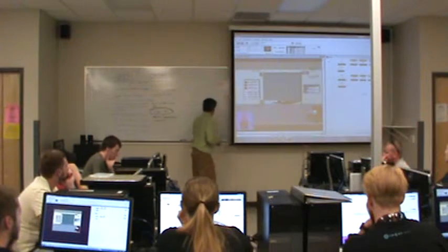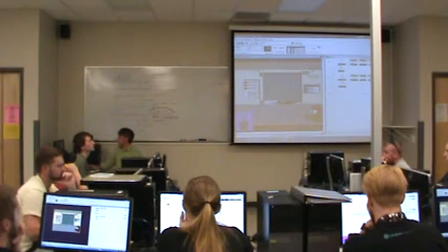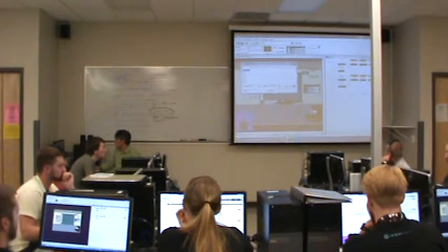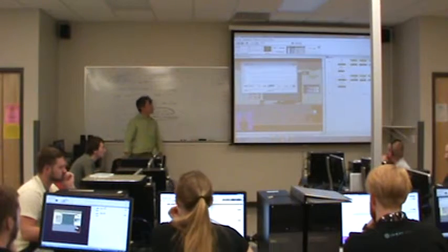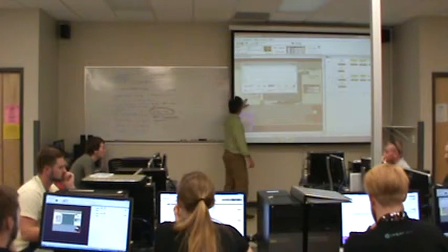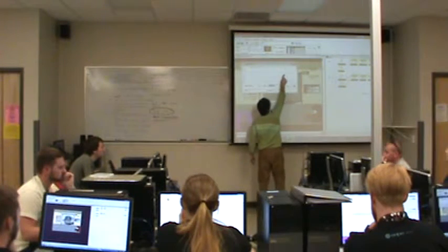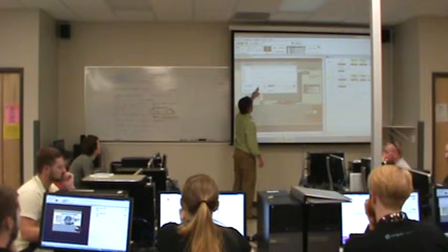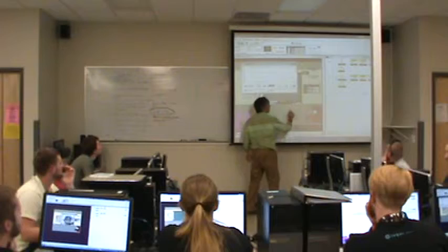All the higher order bits, all the more significant bits, all the other inputs are off. Let me show you where we can find this and show you that this is true. If we go to the data table by clicking the hammer and wrench and go to the inputs file, then you'll notice on the inputs file, which is all on word 1, sure enough, bit 3 and bit 2 are on. Now, if we change this from binary display to hexadecimal display, what do you think is going to be displayed on this row?